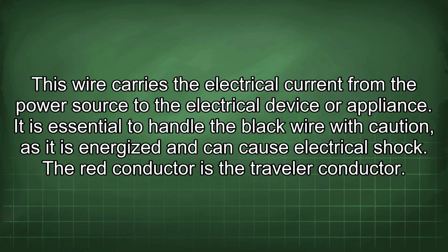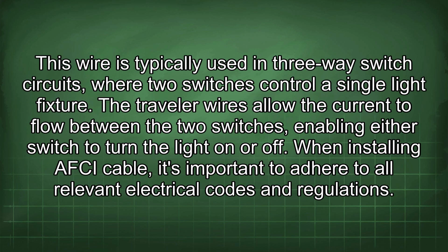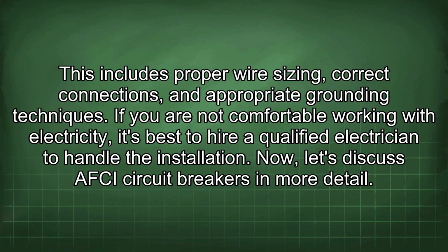The red conductor is the traveler conductor. This wire is typically used in 3-way switch circuits, where 2 switches control a single light fixture. The traveler wires allow the current to flow between the 2 switches, enabling either switch to turn the light on or off. When installing AFCI cable, it's important to adhere to all relevant electrical codes and regulations. This includes proper wire sizing, correct connections, and appropriate grounding techniques. If you are not comfortable working with electricity, it's best to hire a qualified electrician to handle the installation.